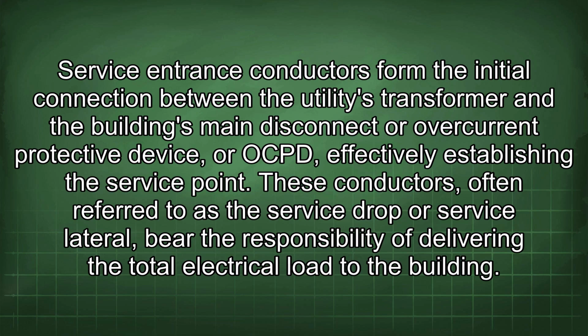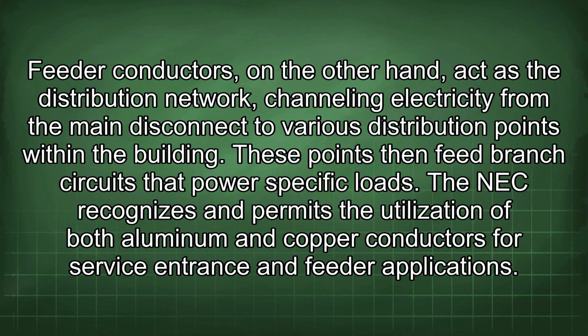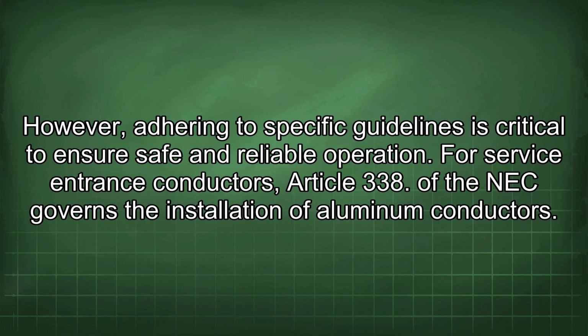These conductors, often referred to as the service drop or service lateral, bear the responsibility of delivering the total electrical load to the building. Feeder conductors, on the other hand, act as the distribution network, channeling electricity from the main disconnect to various distribution points within the building. These points then feed branch circuits that power specific loads. The NEC recognizes and permits the utilization of both aluminum and copper conductors for service entrance and feeder applications. However, adhering to specific guidelines is critical to ensure safe and reliable operation.